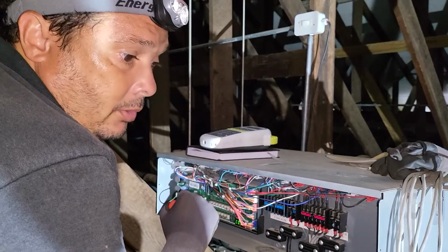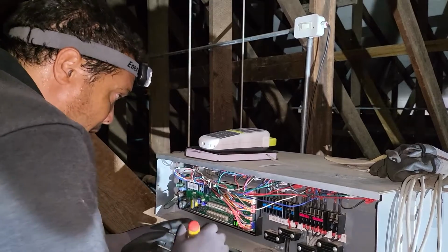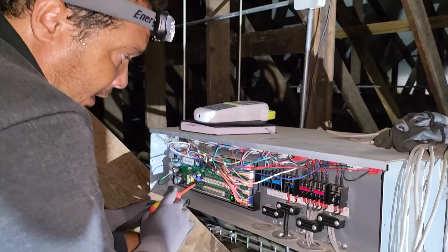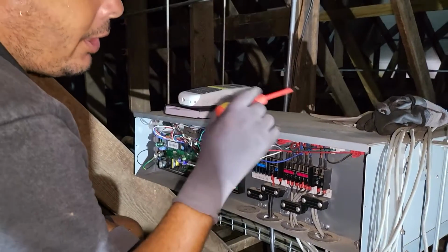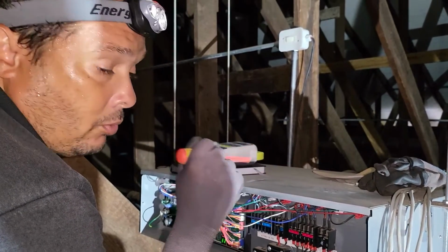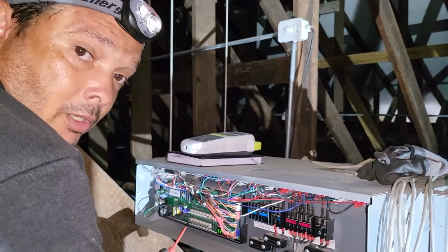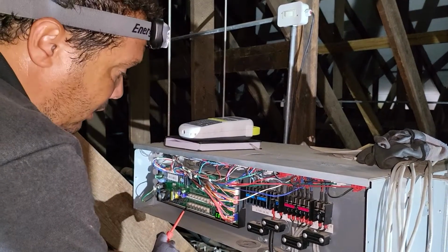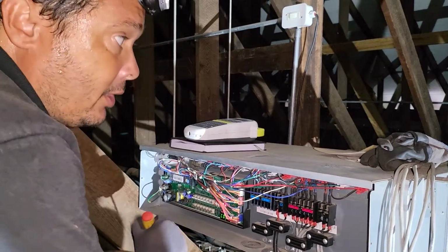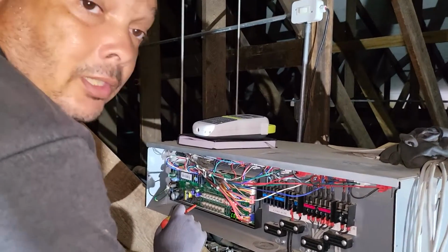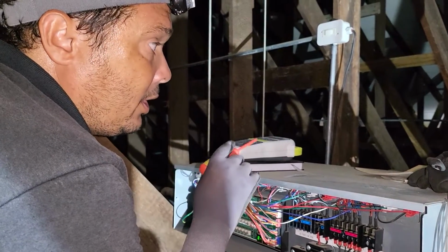Your first 2 sets of circuits are connected into a RefNet joint. So when it comes to the addressing for that sort of setup, you would have an identical address. In the case here we've got circuit A and B going into a branch into one system, which means your addressing at A and B on the rotating dials should be identical. We do have that. They are both set at 10, so the addressing for the first 2 is set at 10, and that's correct.